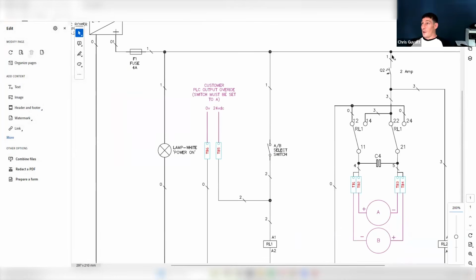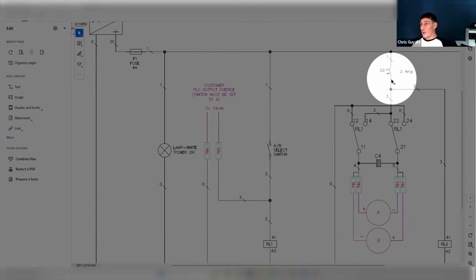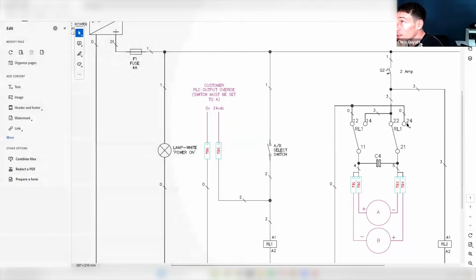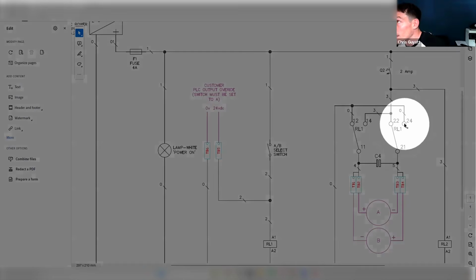Now what happens if we follow it from the top, providing they haven't tripped out? If we go 24 volts down here, we can't go any further because the relay's energized, the contact's switched over here now. So we're not going any further here, but the contact over here is switched to 14, so we're sending the 24 volts down this route onto these terminal blocks.